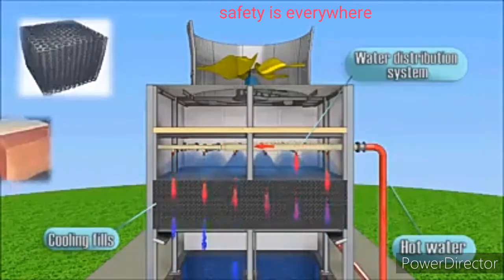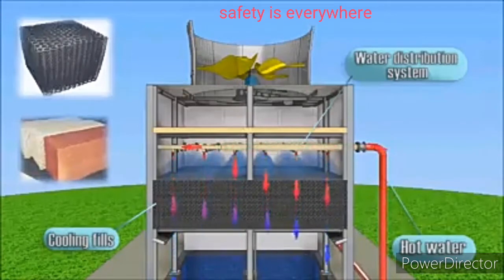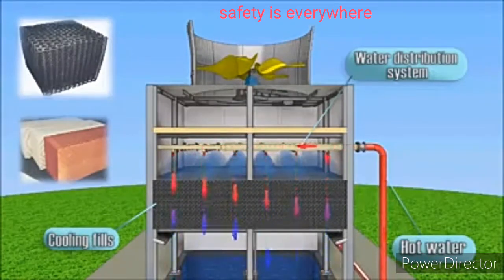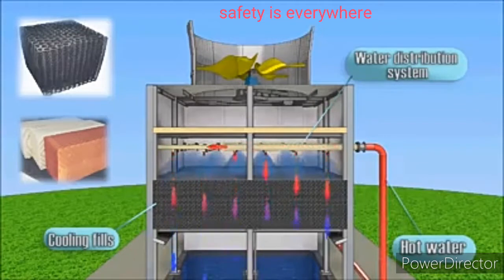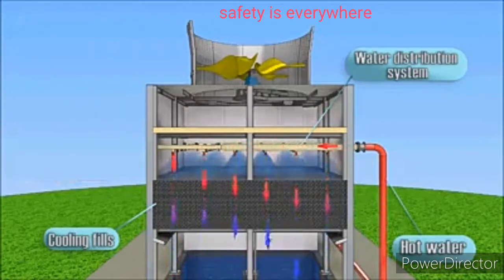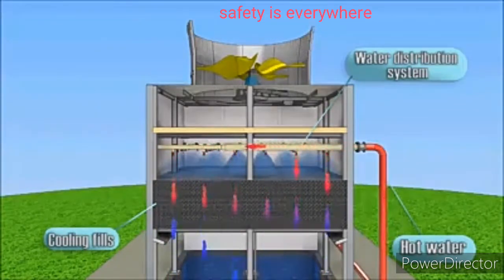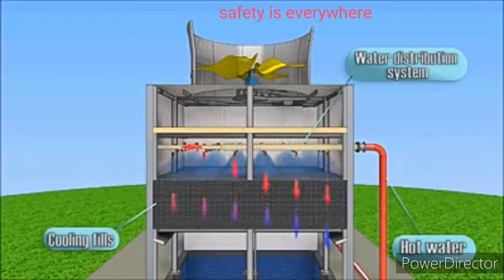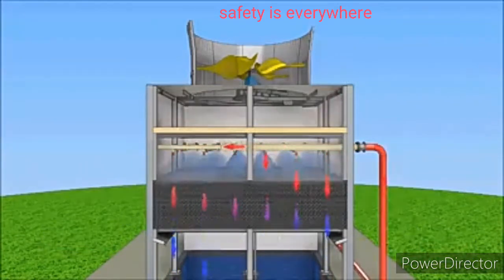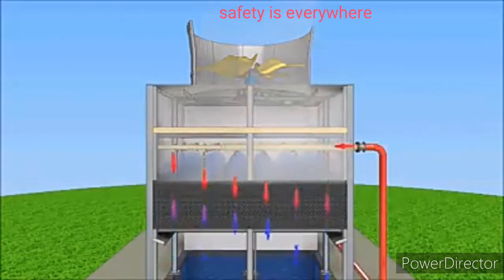On the fills, a water film is formed, from the surface of which the water evaporates and encounters the air flow. The larger the surface area of the fills, the more intensive is the evaporation of water, and the more efficient is the cooling tower. Evaporation is accompanied by expenditure of energy required to convert liquid to vapor. The humidity of the air increases when water evaporates.